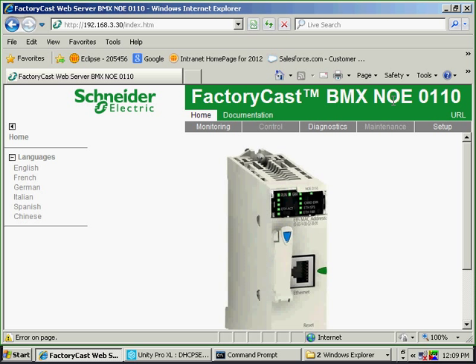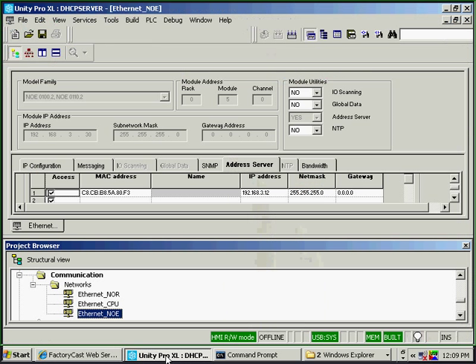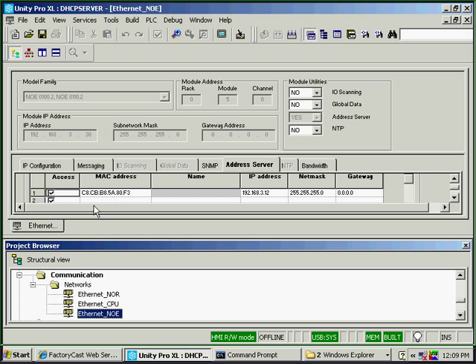So let me show you the configuration in the PLC very quickly. If you configure the Ethernet module for an IP address, just simply turn on the address server. You need to know the MAC address of your PC, and then you give it the address that you want to assign it to.